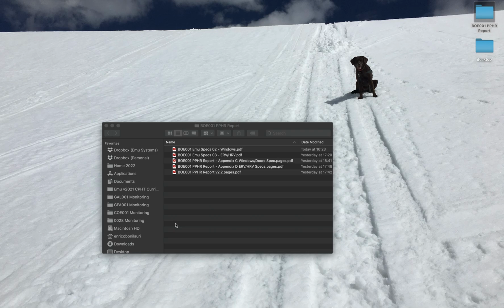And regular HVAC contractors have the hardest time understanding the difference between this kind of fresh air system and how different it is compared to a regular forced air system. Those two systems are very different. We're going to cover that in the Appendix D. But because of that challenge that many HVAC contractors have in understanding an ERV system or HRV system, we provide very detailed specs for the airflow rates of individual registers, as well as how to commission the system once it is installed.